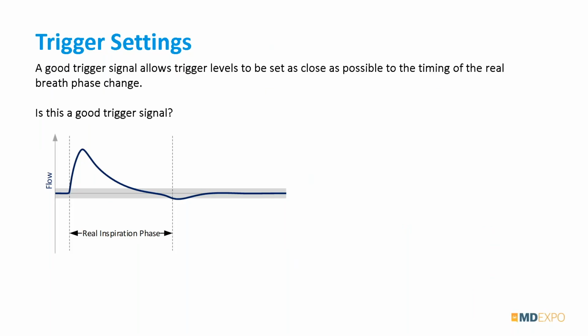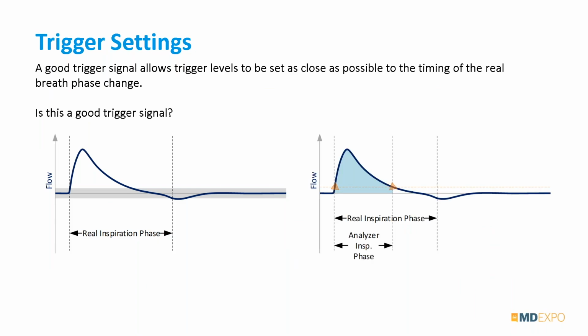Yes, correct. This is actually not a very good trigger signal. At the beginning of the inspiratory phase, it looks pretty good because it has a steep rise. We could say, if it crosses 2 or 3 liters per minute here, then this is the start of our inspiration phase, and that gives us a very accurate trigger, very close to reality. But at the end of the inspiration phase, when it switches to exhalation, there is not really a nice change in the signal, so we can't really set a proper trigger setting there.